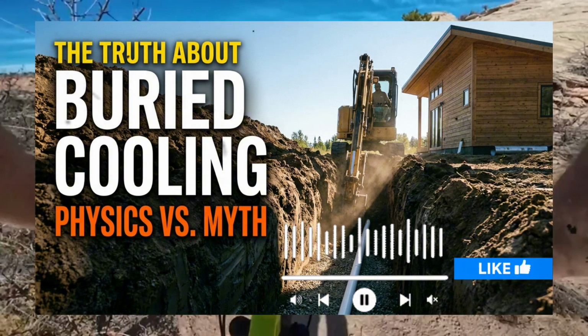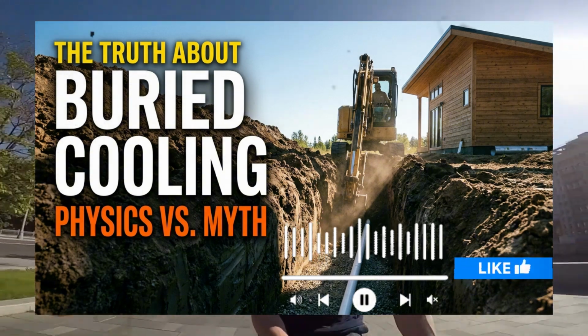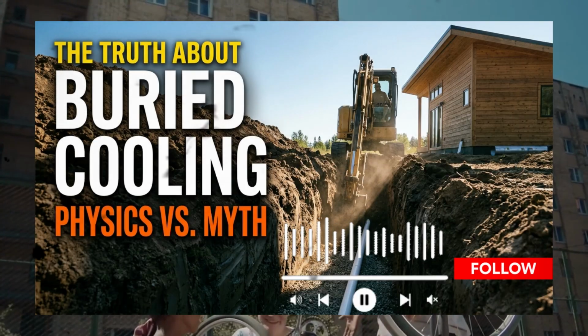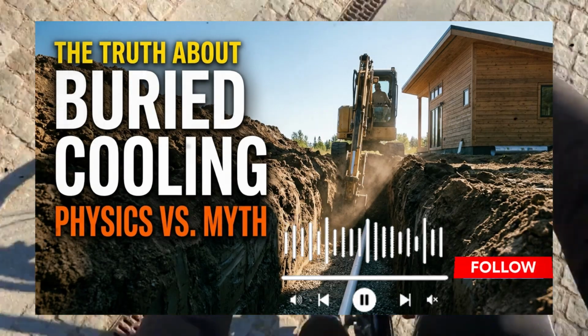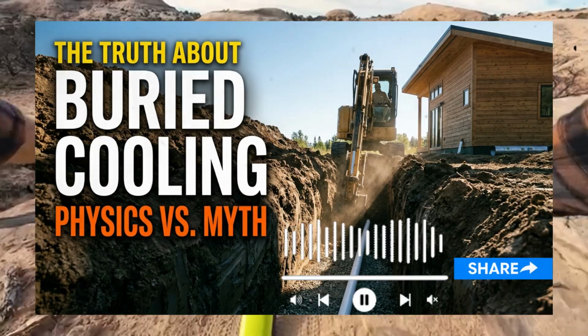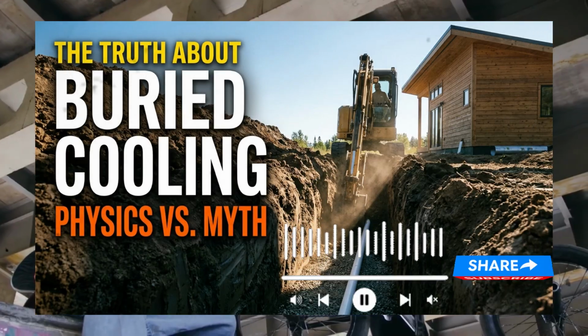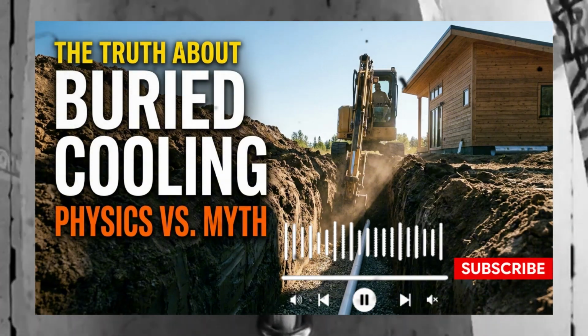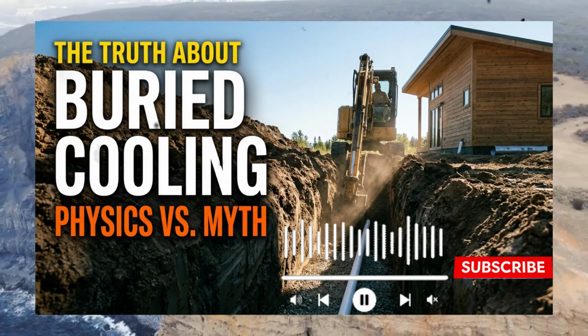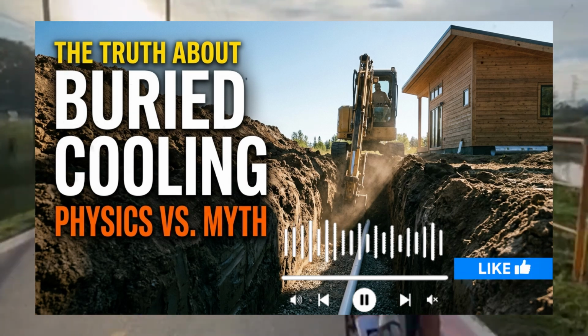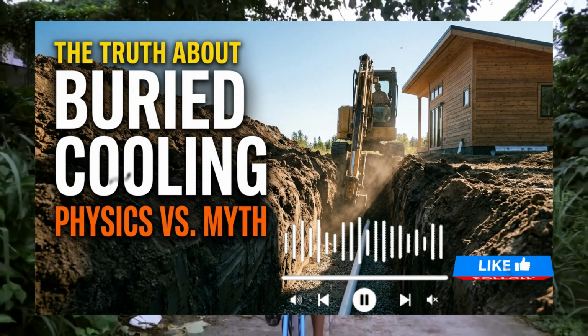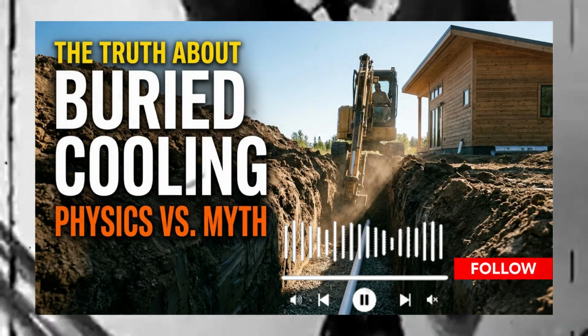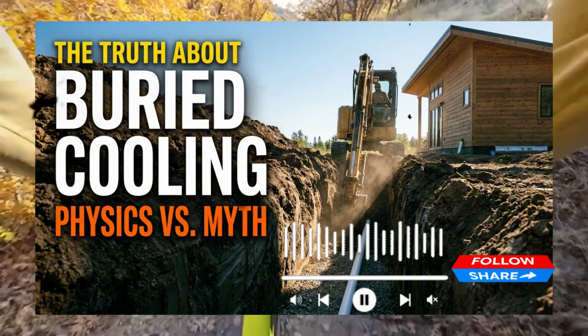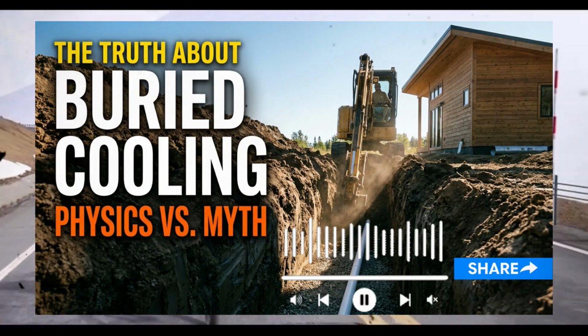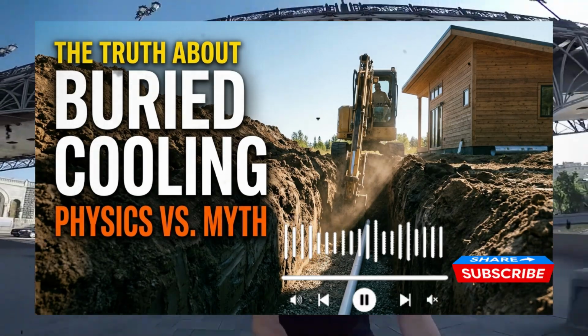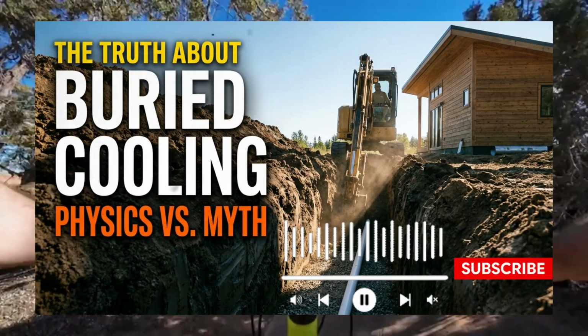At the absolute lowest point of our underground run, right before the pipe turns upward to enter the crawlspace of our home, we engineered a specialized condensation collection chamber. We buried a heavy-duty, watertight vertical sump basin beneath the main run. The main cooling pipe passes directly over this basin, with a secure, sloping T-fitting that allows all condensed water to fall directly down into a gravel leach field beneath the frost line. To ensure that no subsurface water could back up into our air pipe, we installed a mechanical backflow preventer and a small, low-voltage automatic bilge pump inside the basin. This pump is wired directly to a float switch. If the condensation level rises to a critical point, the pump activates silently, lifting the water out of the basin and discharging it safely to a surface drainage swale far away from our foundation.